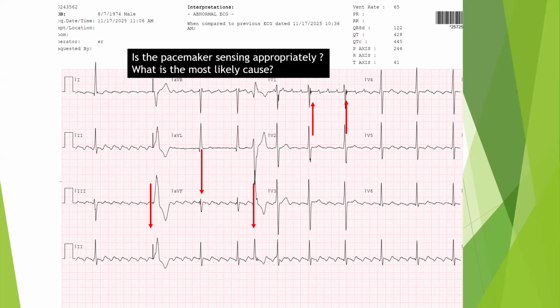Micro lead dislodgement is very common, especially in active fixation leads. During the procedure you screw the lead in well, but the ring of the lead, which most of the time you want to be against the myocardium, changes and becomes at a right angle to the myocardium, and as a result the ring is away from the myocardium. That's why the sensitivity changed. And most of the time here, changing the polarity or lowering the sensitivity can help.